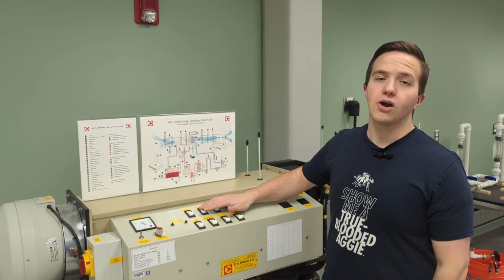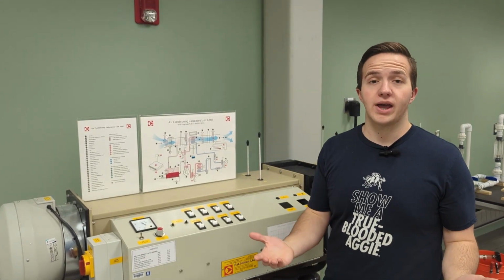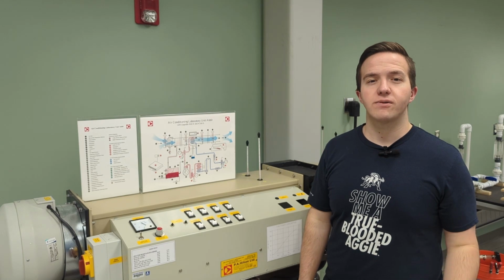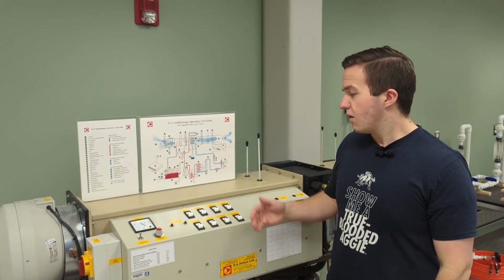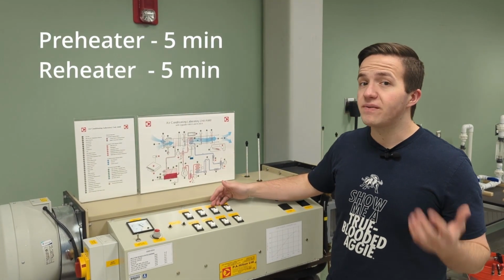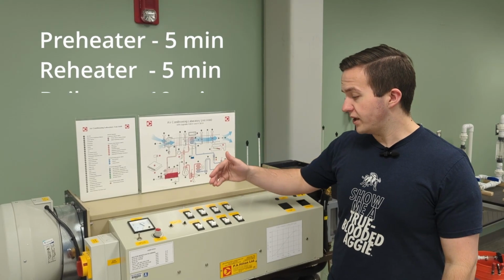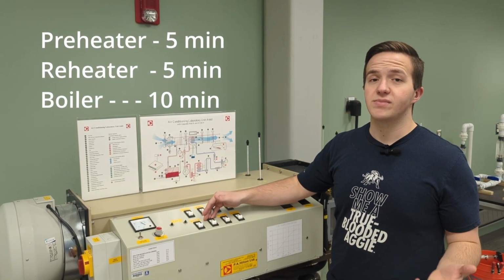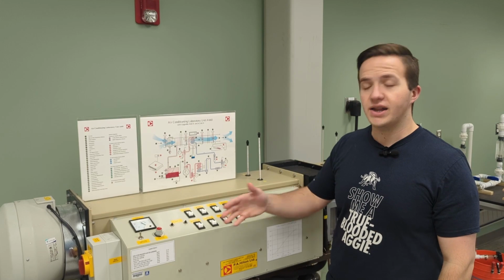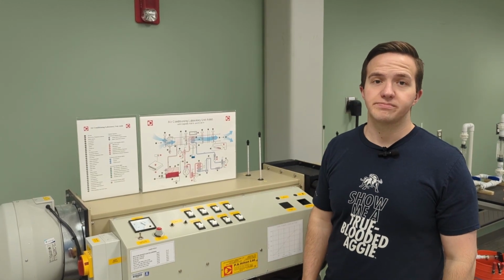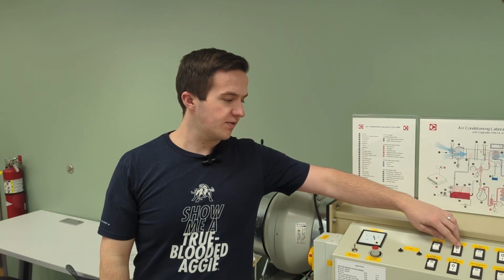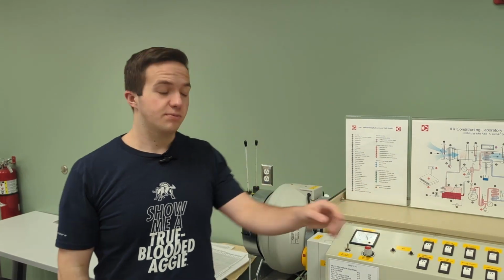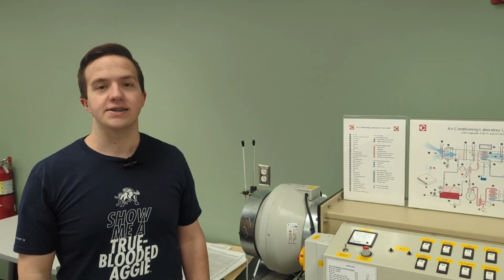After turning on or off any individual heating or cooling element, it is important to allow time for the system temperature to stabilize. For the preheater and reheater, this takes about 5 minutes for heating, and for the boiler heater, this can take about 10 minutes. It takes even longer for any individual part of the system to cool down. Be sure to turn off each individual heating and cooling element, as well as the HVAC machine as a whole, when testing is completed.